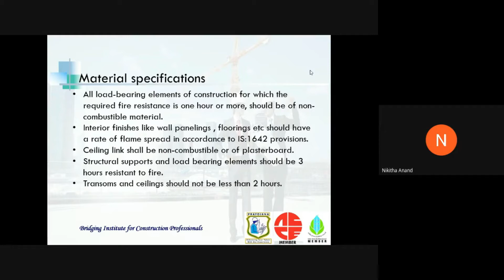The ceiling lining should also be non-combustible or of plasterboard, because the ceiling also plays a major role in a building. It might be the connection to another floor also. So it should be taken care that it is non-combustible. And when it comes to structural support and load bearing elements, they should have 3 hours of resistance to fire, and transoms or ceiling should have not less than 2 hours of fire resistance.